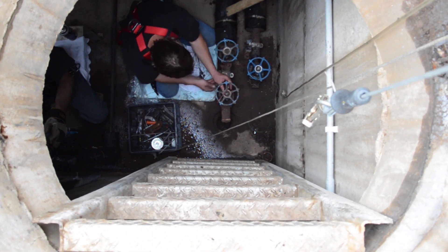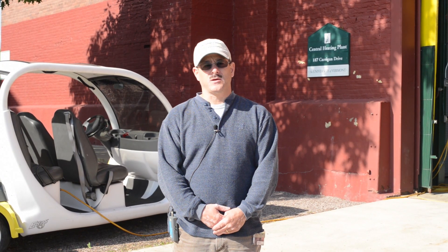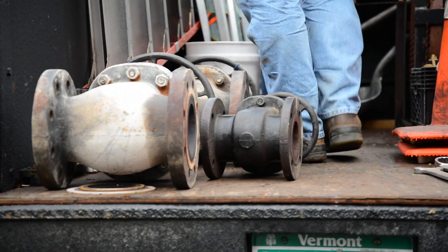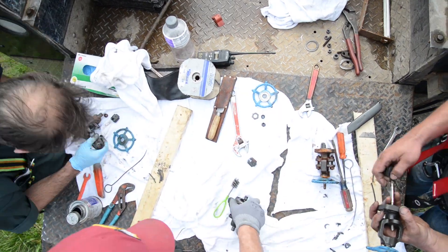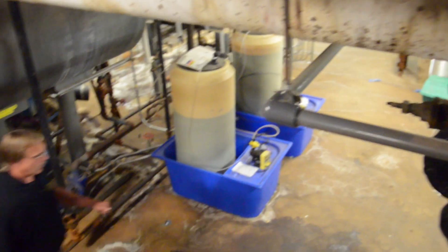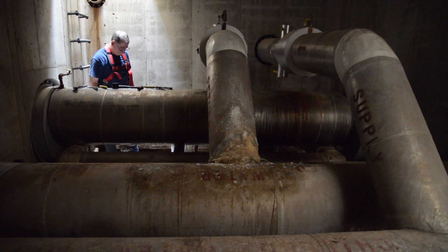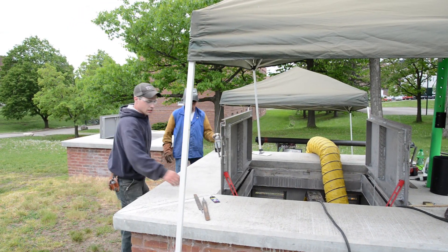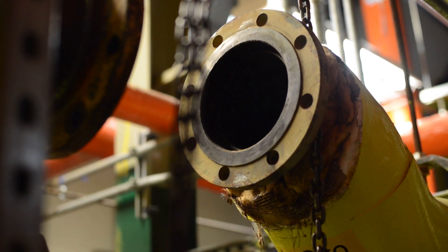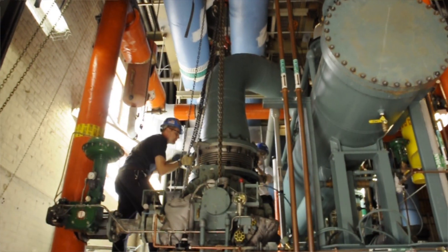At this point in time, we have about 40 vaults we pull maintenance on. Part of the maintenance is we go in and make sure all the valves are operating, all the trap stations are operating — if they're not, we replace them. We pack the valves. We also have about 24 steam stations in the buildings on campus that we do maintenance on, about six miles of high-pressure steam piping underground, and about a thousand steam traps that we're doing maintenance on during the shutdown.